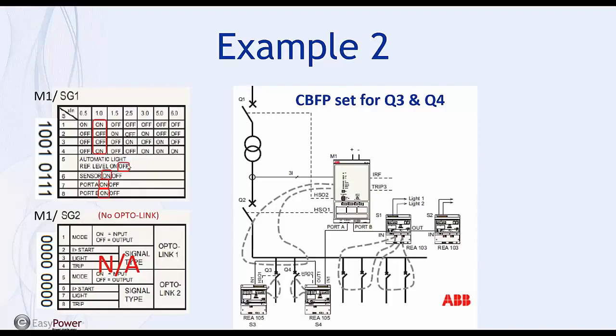The same as before on the pickup, and then no backlight compensation. You're activating your sensor, and once again we're now using the port A and B for our extension units, so these will be on. Otherwise it's the same as before. We're not connecting to another main unit, so we don't have to worry about the settings for the optolinks.